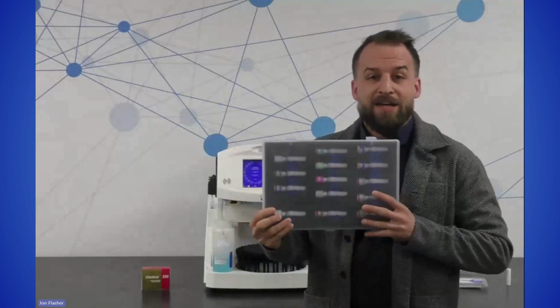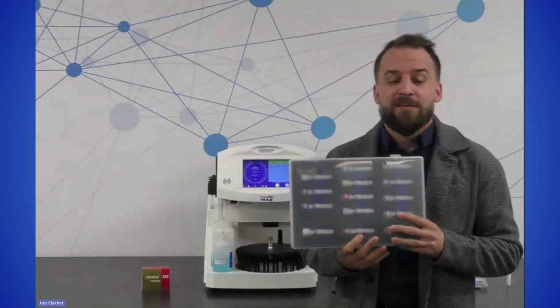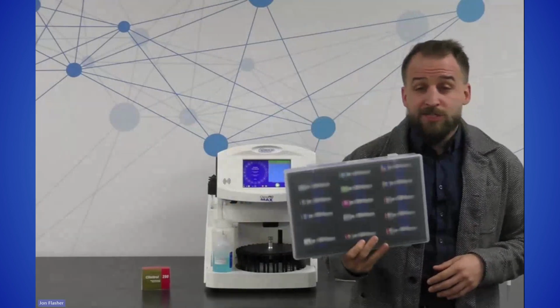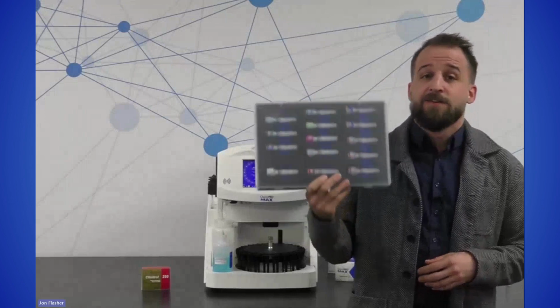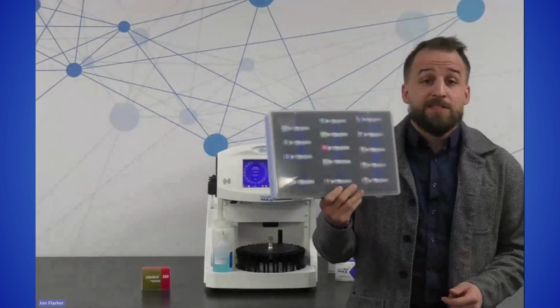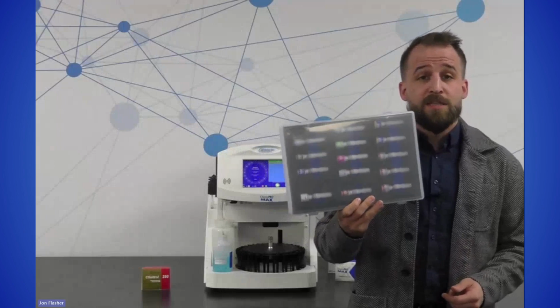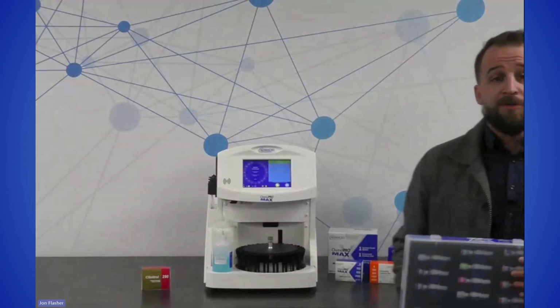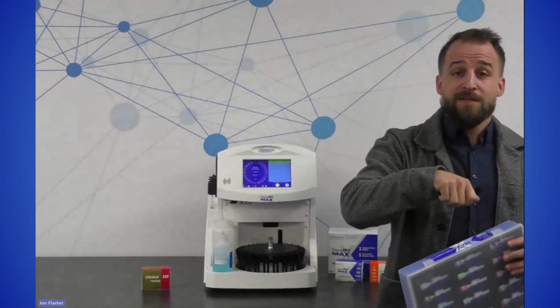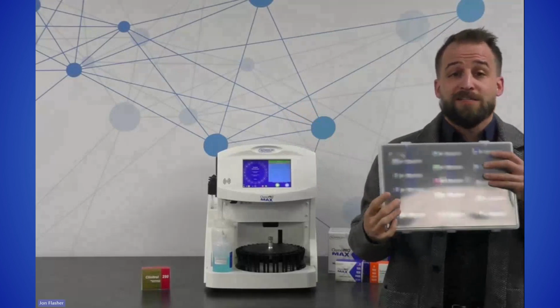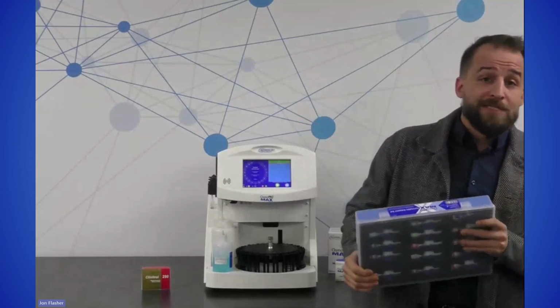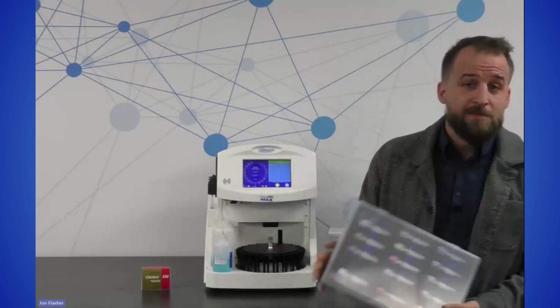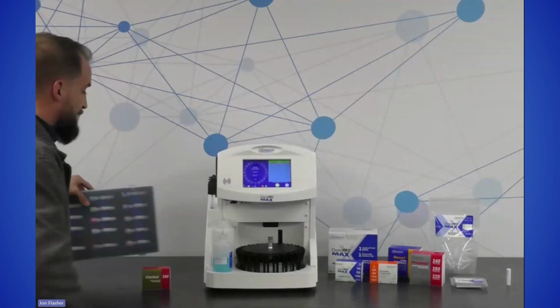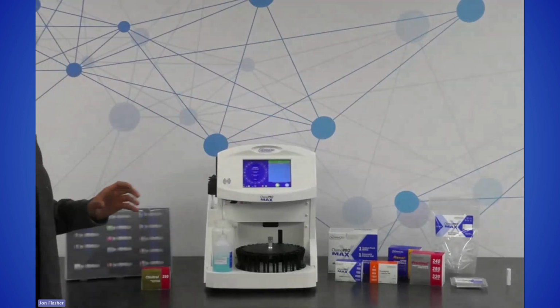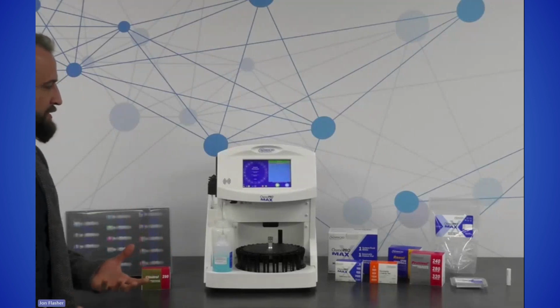Another thing that the instrument comes with is this nifty looking little case over here, and these are actually ampule adapters. So instead of having to manually program or scan in every calibration standard, QC standard, or enzymatic cleaner vial, you can basically just load one of these adapters into the position that you need on the turntable. You can crack the top off of your ampule, put it in the adapter, and hit go. Then it will immediately recognize the barcode that's wrapping one of these adapters and know exactly what it's testing and in what position it's testing it at. So super helpful just to make things easier and add to the benefit of the automation that we've put into this instrument.